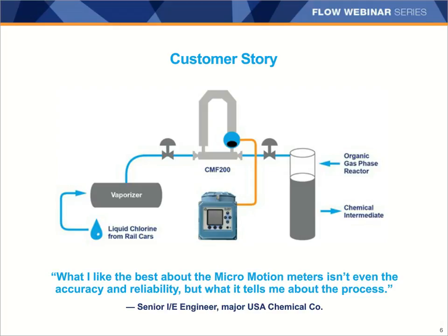Another benefit they saw from switching to Coriolis from the DP meters were significant reductions in potential leak points. With each of the DP meters that were in place before, they had 7 potential leak points with the impulse lines and different connections on the orifice meter. With the Coriolis meter, there were only 2 potential leak points, one at the inlet and one at the outlet process connection. Reducing leak points is really critical for chlorine gas and some other gases as well, but chlorine gas because of its inherent dangers.